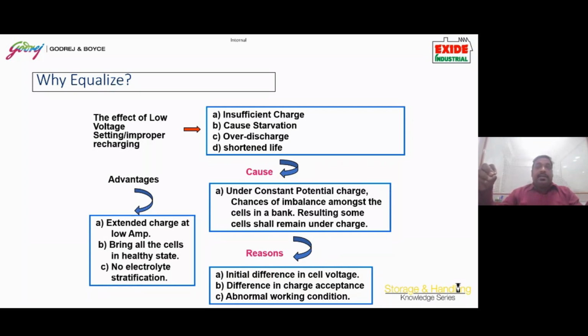Since the current is constant, it will try to charge the cell with the lowest potential difference, while the charge on the other cells will not increase further. So when you come back after the weekend or after a 3 to 4 hour break, you will see that not only the specific gravity but also the voltage of the cells have stabilized, meaning the battery has been put into 100% usable capacity.